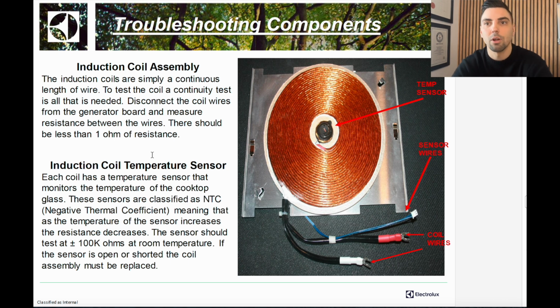So now let's look at some troubleshooting components. Here we're going to look at the actual induction coil. We see here in the middle we have the temp sensor, the sensor wires as well, and the coil wires. So, the induction coil assembly. The induction coils are simply a continuous length of wire. To test the coil, a continuity test is all that's needed. So disconnect the coil wires from the generator board and measure resistance between the wires. There should be less than 1 ohm of resistance.